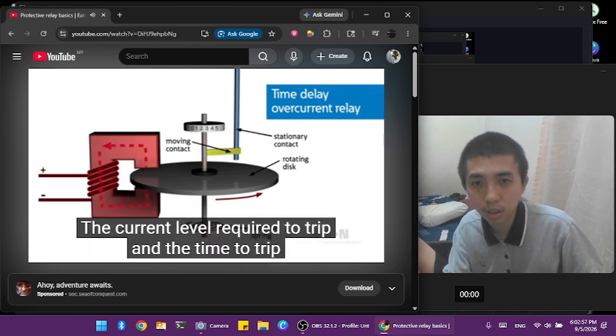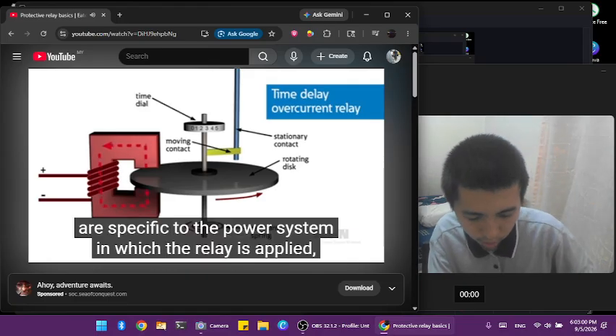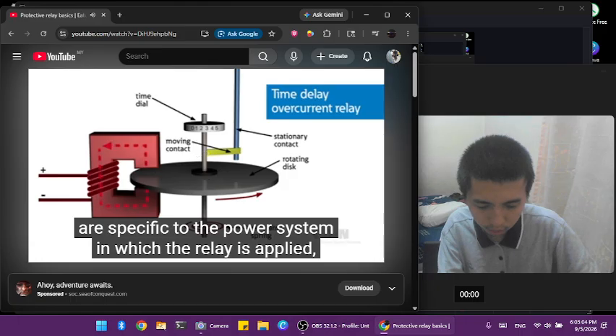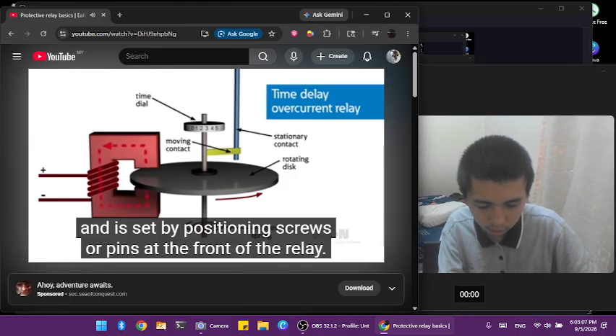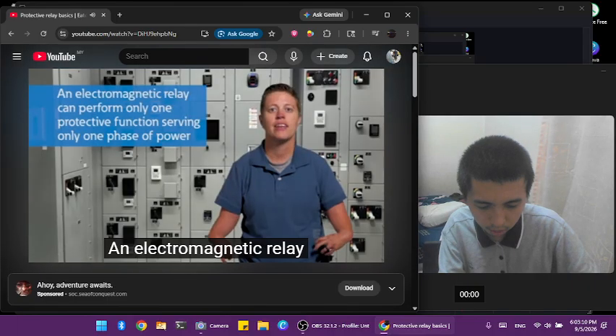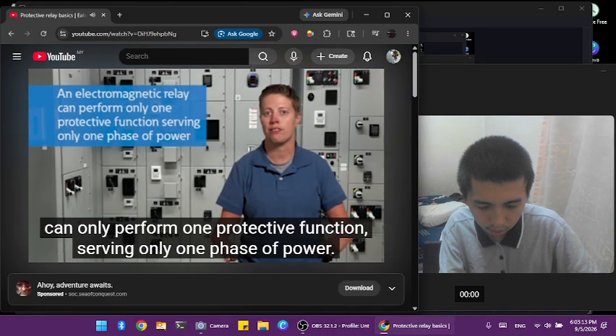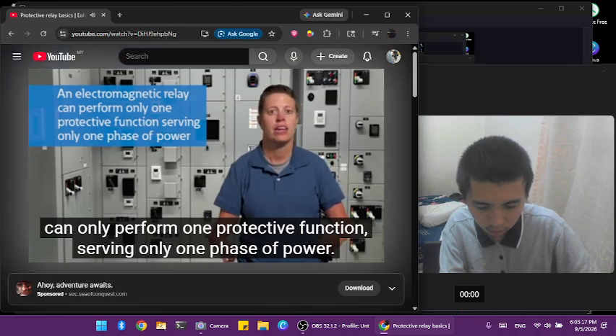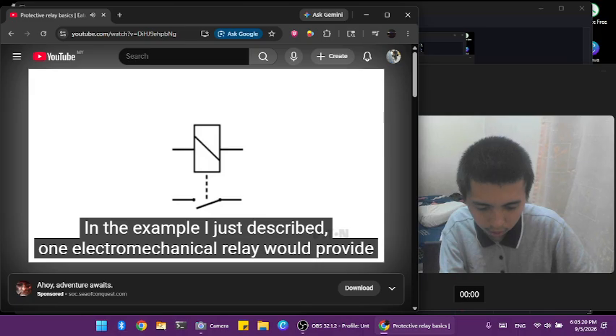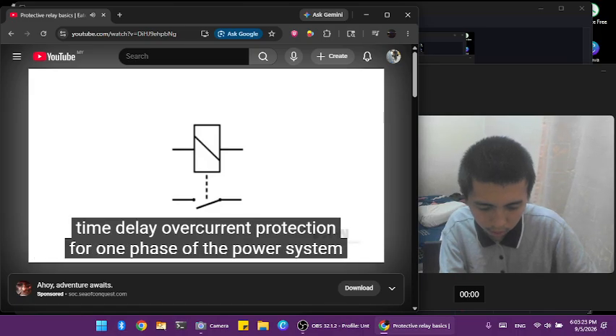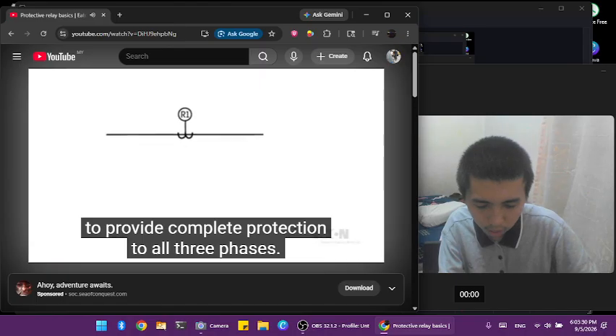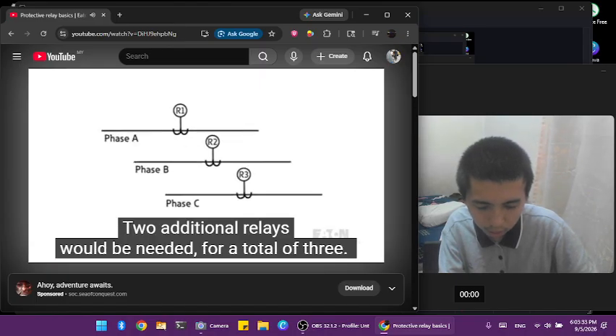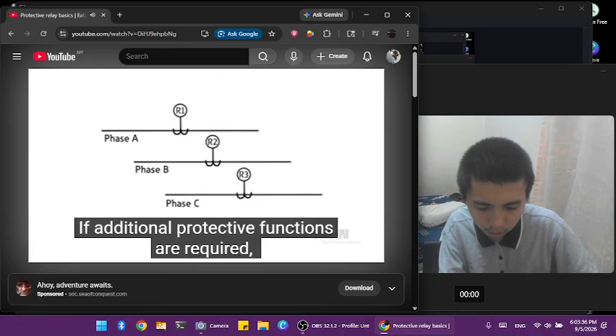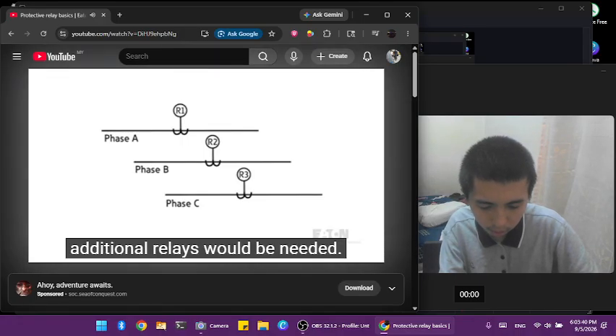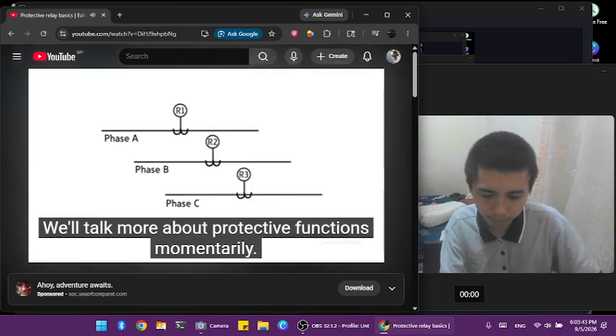The current level required to trip and the time to trip are specific to the power system in which the relay is applied, and is set by positioning screws or pins at the front of the relay. An electromagnetic relay can only perform one protective function, serving only one phase of power. In the example I just described, one electromechanical relay would provide time delay overcurrent protection for one phase of the power system. To provide complete protection to all three phases, two additional relays would be needed for a total of three. If additional protective functions are required, additional relays would be needed. We'll talk more about protective functions momentarily.